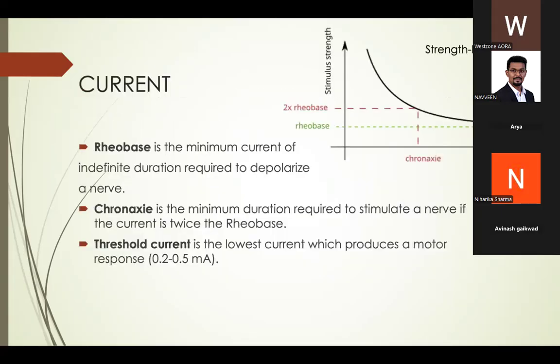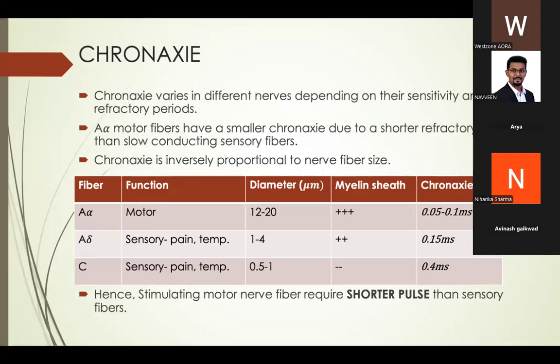So, coming to the current, there is a term called rheobase, which is the minimum current of indefinite duration required to depolarize a nerve. And chronaxie is the minimum duration required to stimulate a nerve if the current is twice the rheobase. And the threshold current is the lowest current which produces a motor response, which is 0.2 or 0.3 to 0.5 milliamperes. So chronaxie varies in different nerves depending on their sensitivity and the refractory periods.